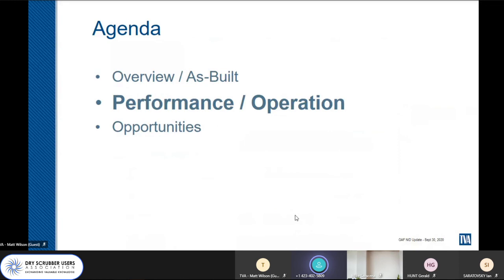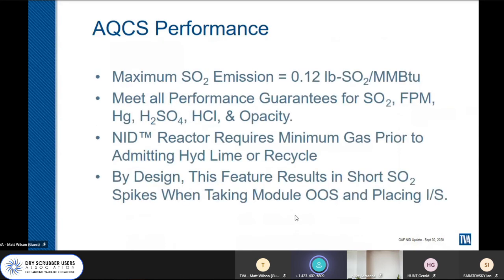Now for performance operation. The performance guarantee for maximum SO2 emission was 0.12 pound of SO2 per million BTU. The system met all performance guarantees for SO2, filterable particulate matter, mercury, sulfuric acid, hydrochloric acid, and opacity. The NID reactor requires a minimum gas flow before admitting the hydrated lime or recycle. We already talked about that, and I've got another slide on it. By design, this results in some short SO2 spikes when taking the modules out of service and placing them in service.